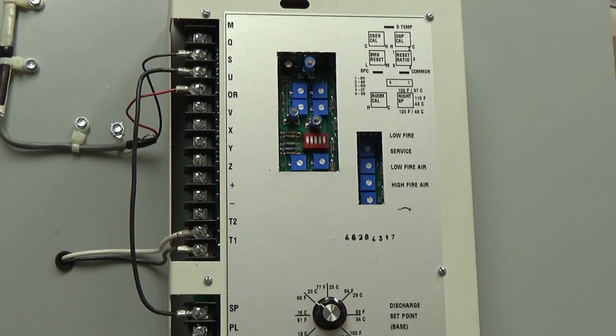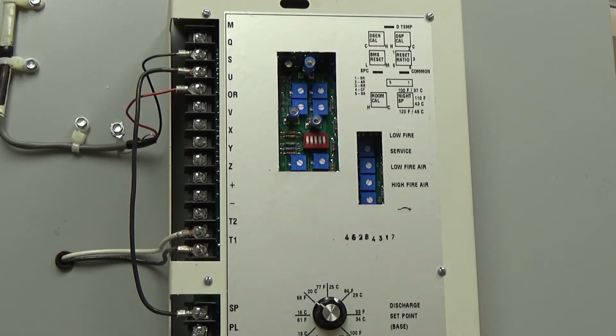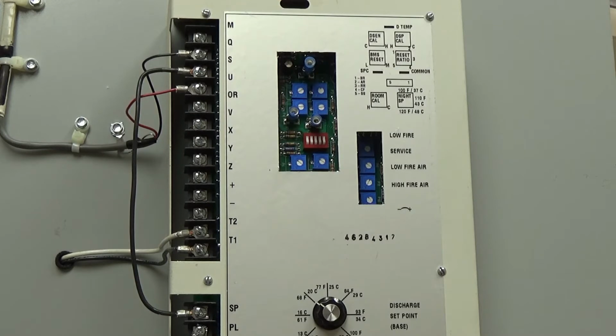The base set point dial on the GTRAC2 is activated when terminals S and SP are jumped and no discharge air resets are activated, or dip switches 1 through 5 are in the off position. If you have a remote panel with set point and no resets, terminals S and SP are not jumped, and the remote panel set point dial is wired to terminals M, S, and U. Whether you have a base set point or remote set point, the calibration method I'm about to show you is the same for both.